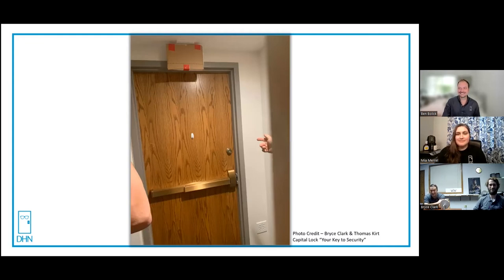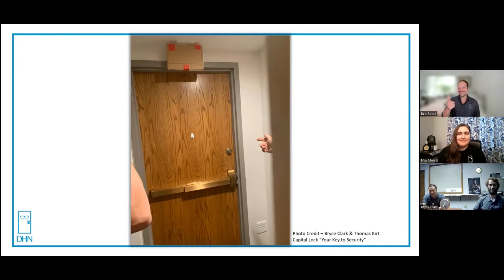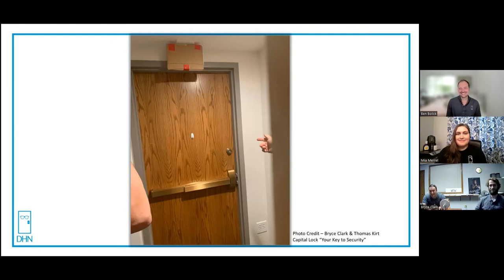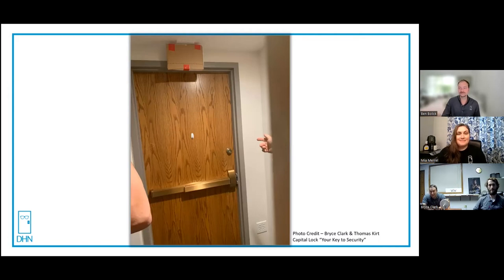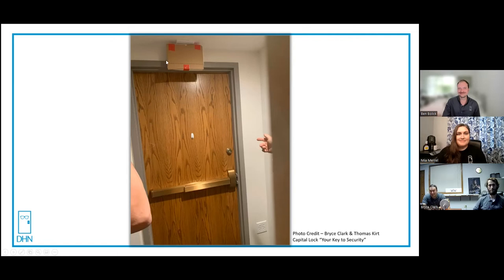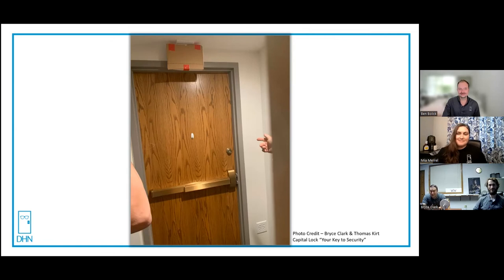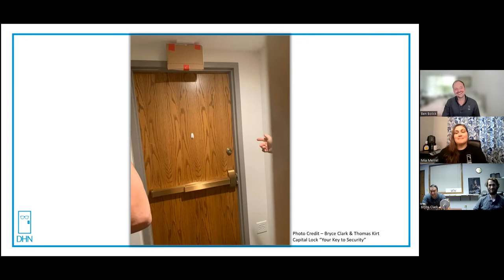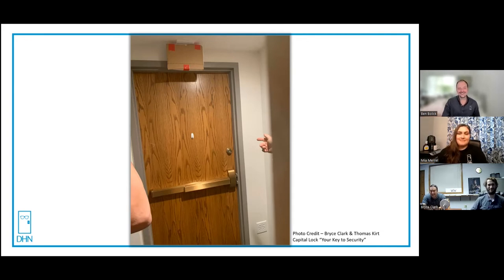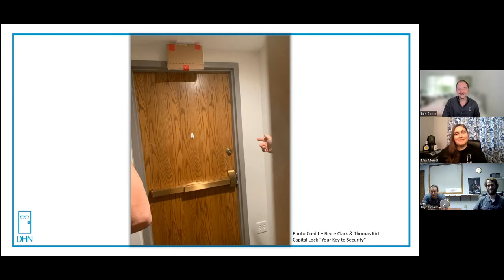So, the background story on this one, I was the one who took this picture out in the field. You can see one of our techs pointing at it directly and laughing there. He's the one with 30 years of experience out in the field. So, this is a fire door into the stairwell. As you can see, there is a deadbolt on there. And then, where the exit sign is supposed to be displayed, they crudely taped a cardboard cutout over. So, it used to be a library. And they were renting out the basement to people who play Dungeons and Dragons. And they didn't want the Dungeons and Dragons people to be able to access the other levels and come up. It has since then been bought out by a medical clinic.